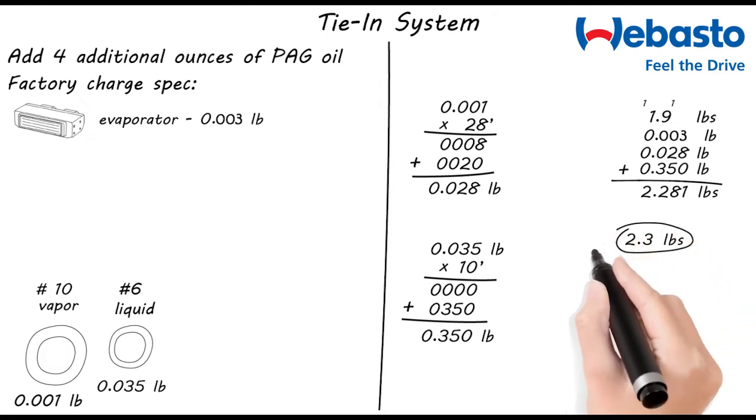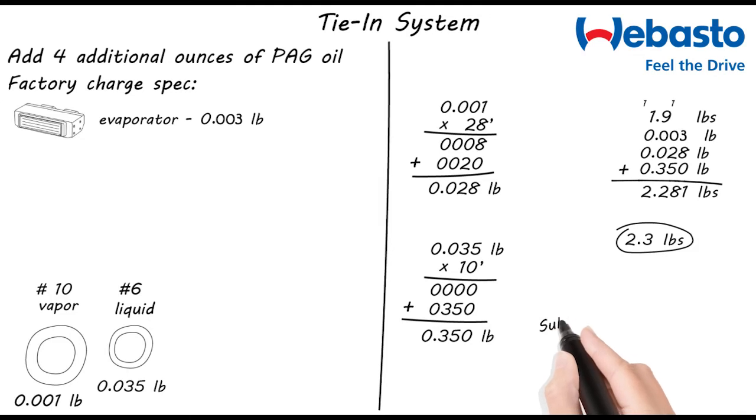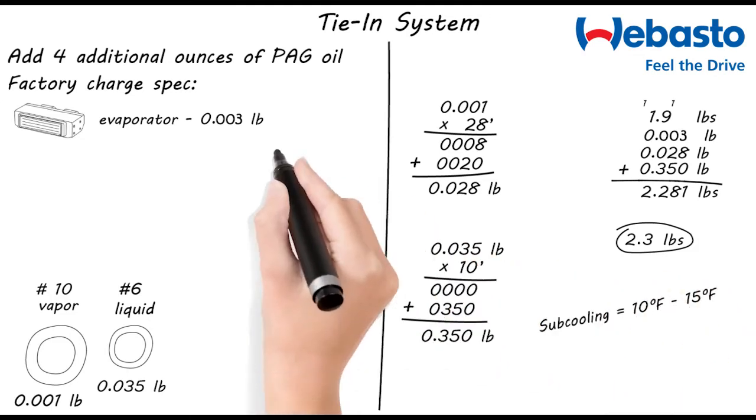But remember, this is just a base charge. You'll adjust this number as needed to achieve 10 to 15 degrees of subcooling. And don't forget to add that PAG oil to the charge.